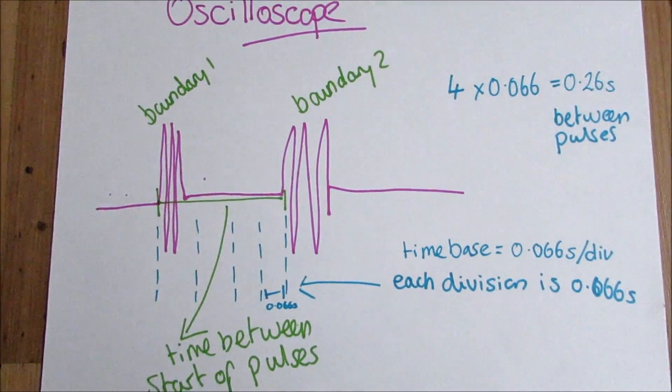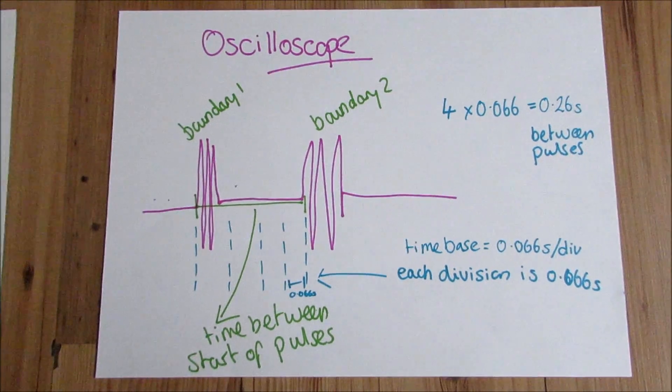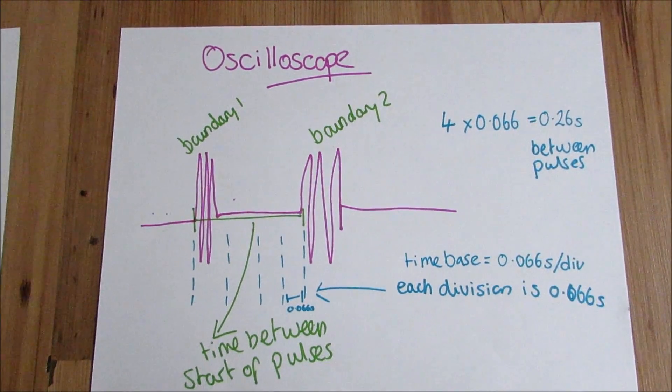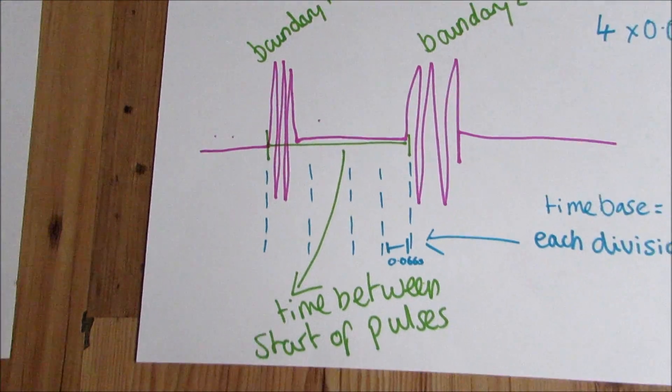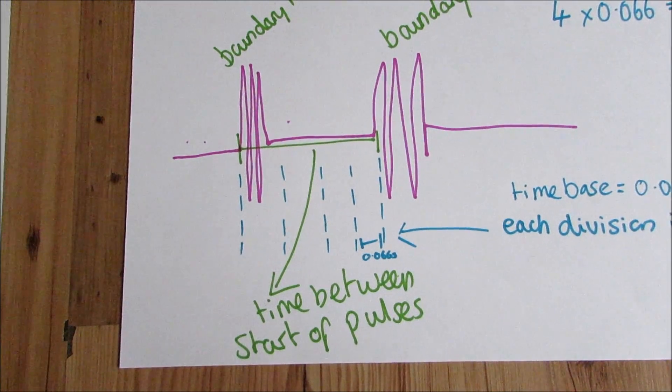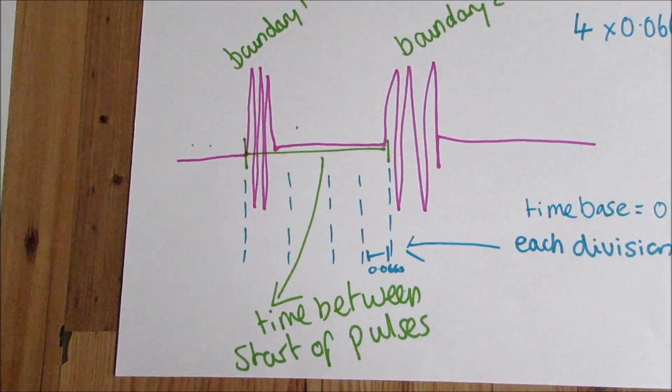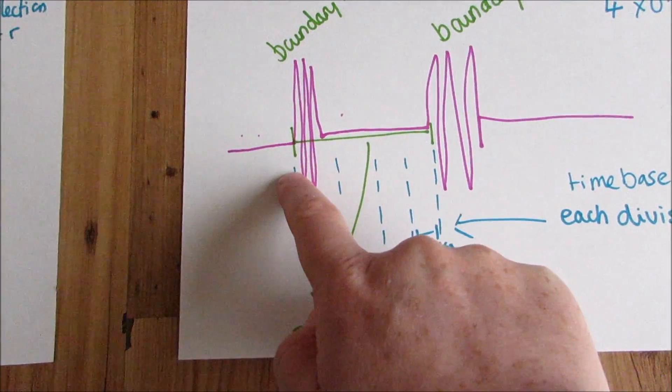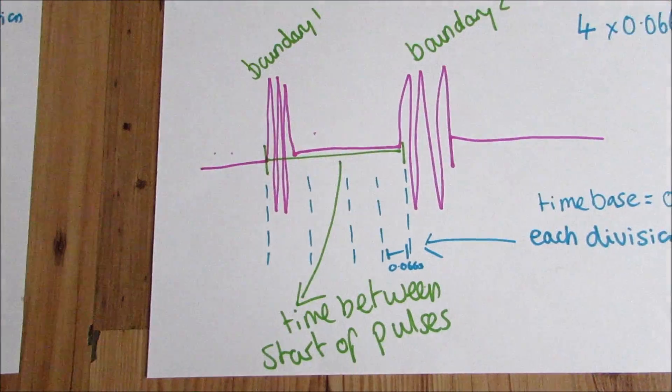This is what the trace will look like on what we call an oscilloscope. This is just a piece of equipment connected to the computer that will show you what your ultrasound looks like. We've got boundary one and boundary two. On the oscilloscope, there will be a grid, and this will be the time base. What we want to find is the time between the start of each pulse.